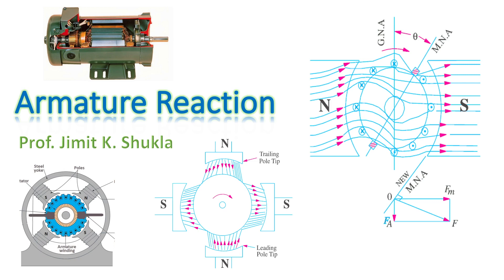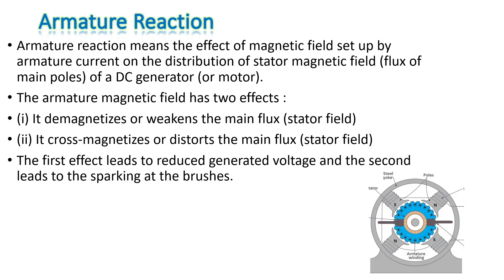We will learn about armature reaction in DC machines in this video. Armature reaction means the effect of magnetic field set up by armature current on the distribution of stator magnetic field or flux of the main poles of a DC machine, be it generator or motor. This armature magnetic field has two effects on the main flux: it demagnetizes or weakens the main flux, and it cross-magnetizes or distorts — that means it changes the direction of the main flux.